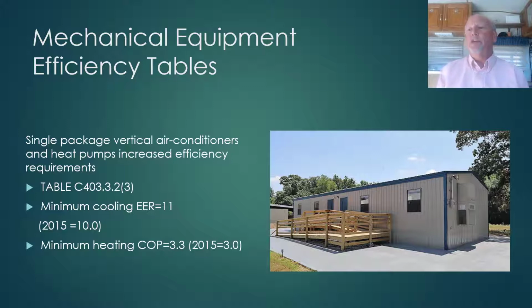First of all is single package vertical air conditioners and heat pumps. The efficiency values of that equipment have increased about 10%. So the minimum cooling efficiencies have increased to an EER of 11. It was previously 10.0, and the heating COP for heat pumps has increased to 3.3. It was previously 3.0. And this is worth noting because single package vertical AC and heat pumps are commonly used on equipment buildings, portable buildings, small commercial buildings, temporary buildings, and because there are many energy codes across the United States, you can still purchase equipment that has an EER rating of 10, so equipment that does not comply with the code. So just a heads up that if you're going to be specifying or working on projects that use single package vertical AC units or heat pumps, there are changes to the minimum efficiency requirements.